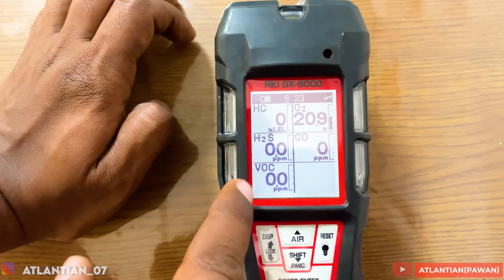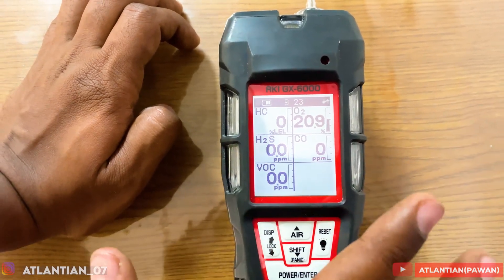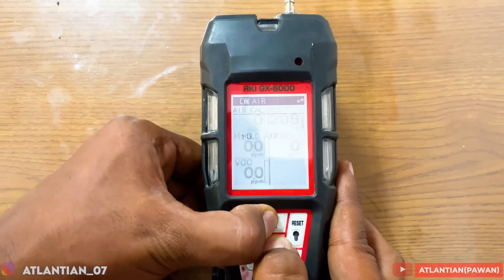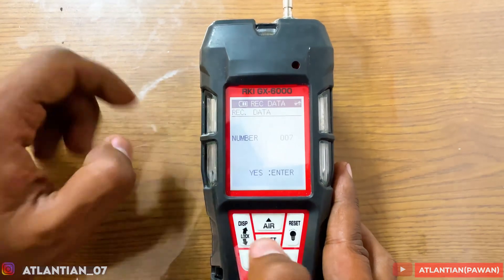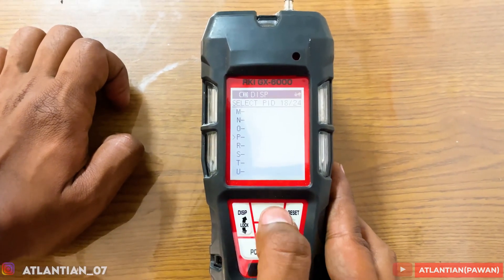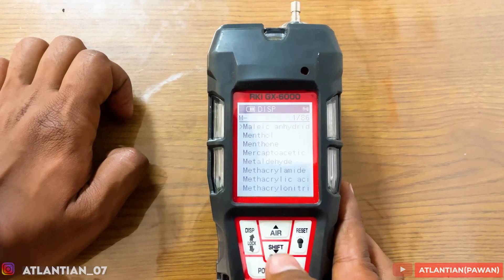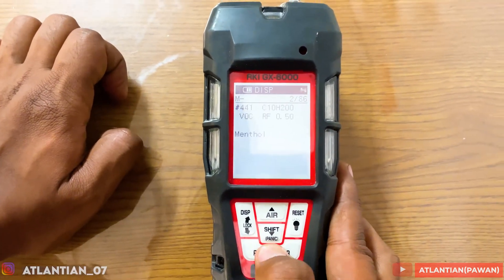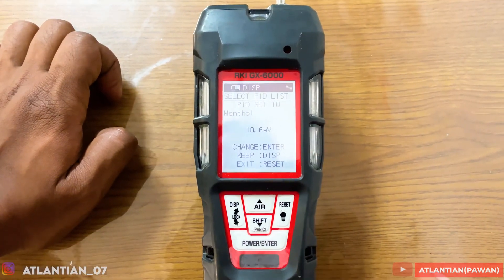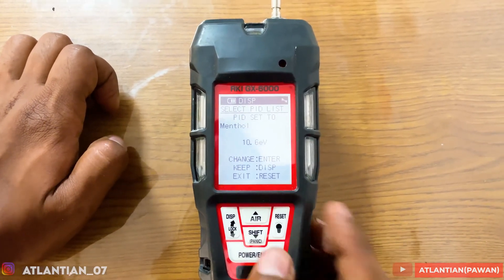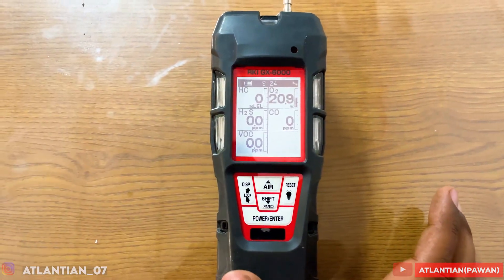Now in the left column, VOC, if we detect anything it will show the reading for Phenol. In this way we can select or deselect any gas. If I want to change back to Menthol, I press Air and Shift, then Display, then Display again, press Enter, navigate to M, press Enter and select Menthol. Now Menthol is selected, and when I exit the VOC column will show the reading for Menthol. That's how we select gases in the GX-6000.